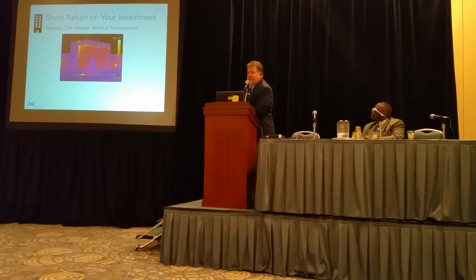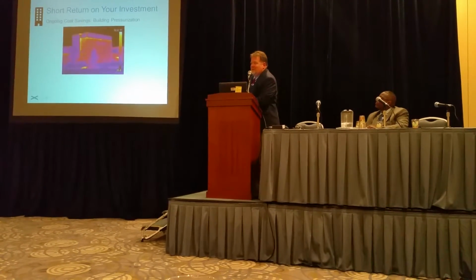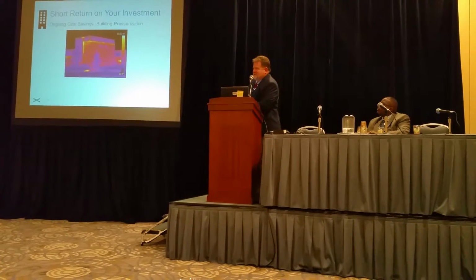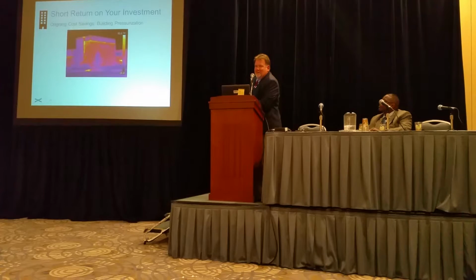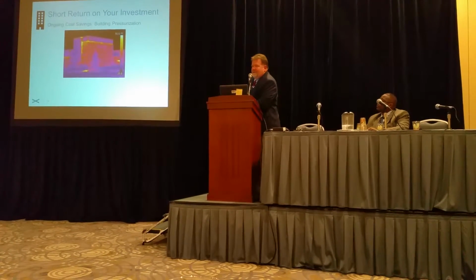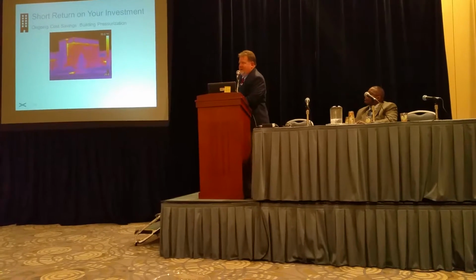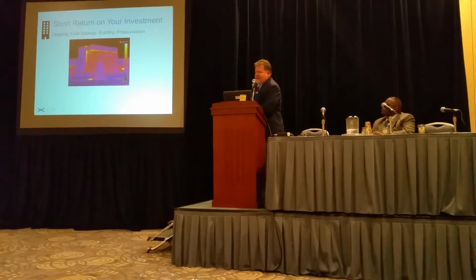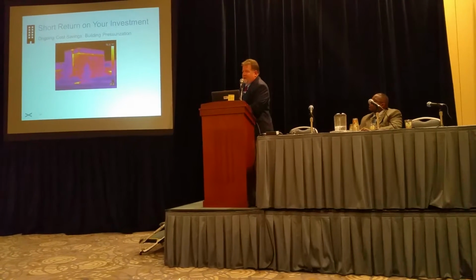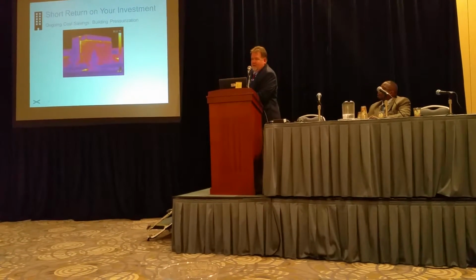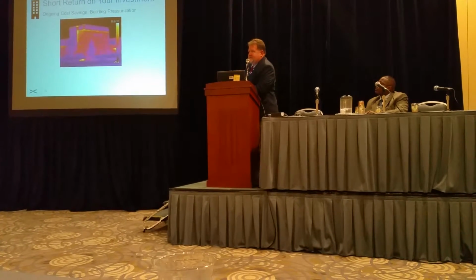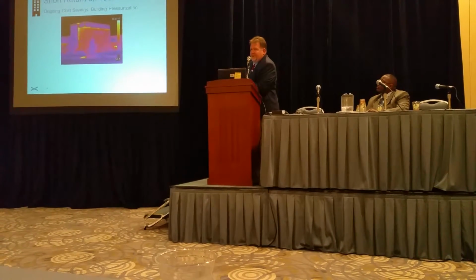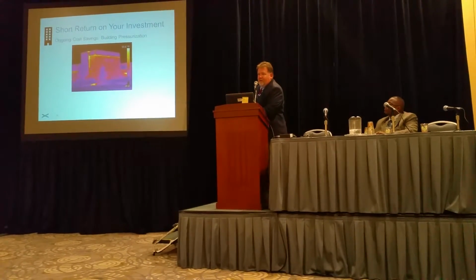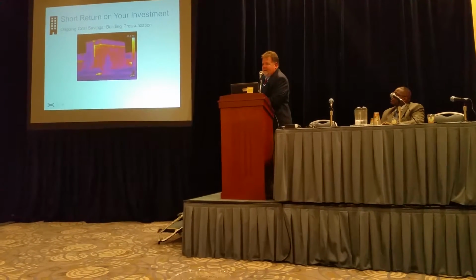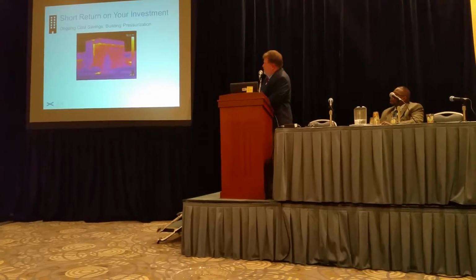Building pressurization, something that's overlooked. Every once in a while you walk into a restaurant and can't open the door because we're exhausting so much air out of it, and we all get it, we feel it, we're in a business, we know what it is. We have it where we're pulling air in through mortar joints, through cracks in the windows, glazing, through everything. Or we're bringing too much air into the building where we have to heat and cool it and we're overpressurizing the building. It is so important to take care of your building pressure. Put multiple sensors in there tied into your building automation system and really have the building running the way you want it to. Huge cost savings. I can't tell you how important it is to do that.